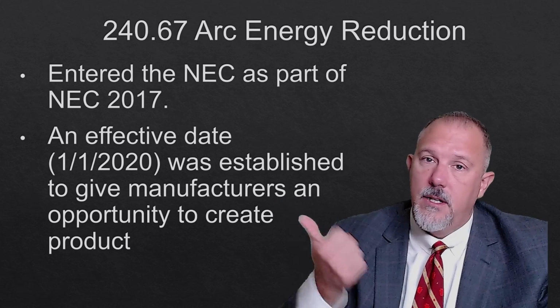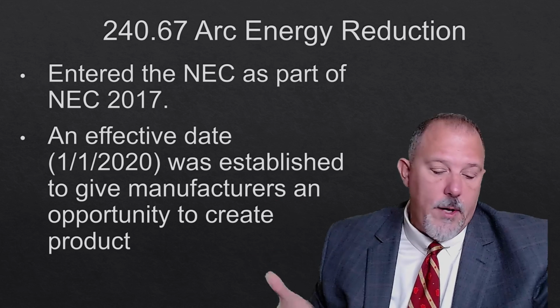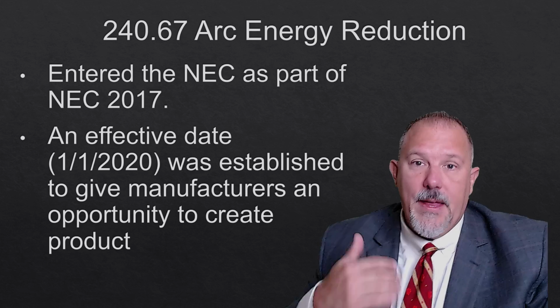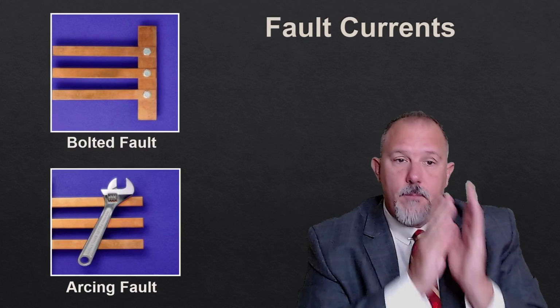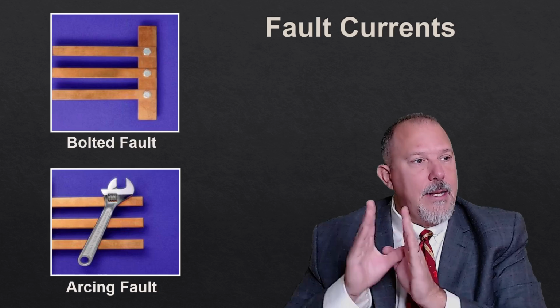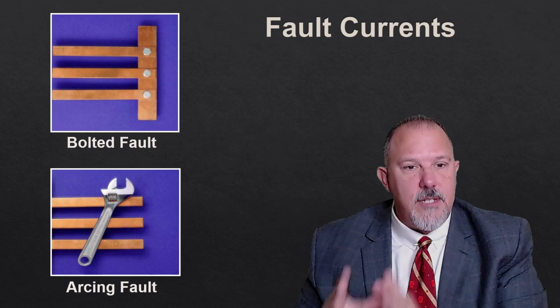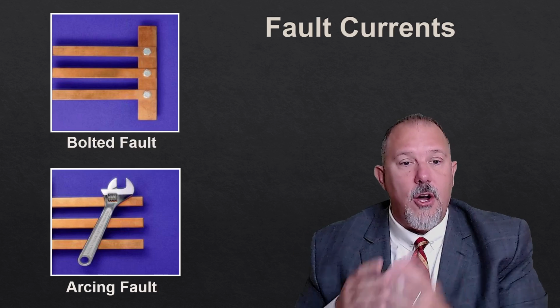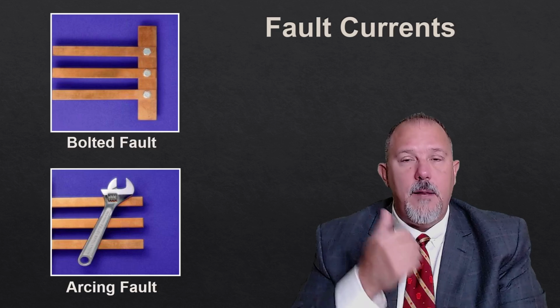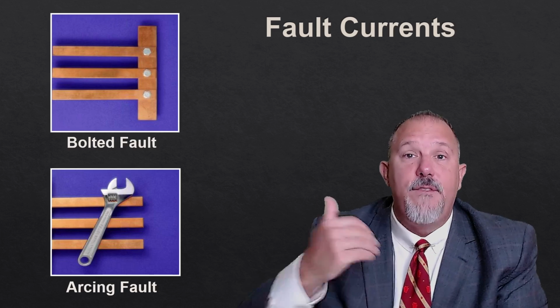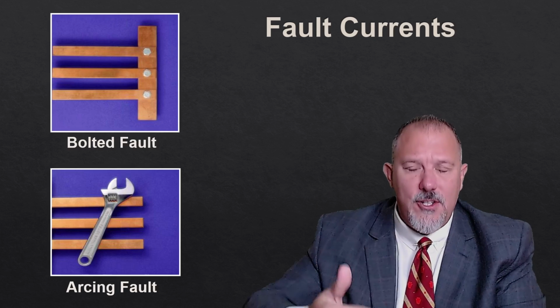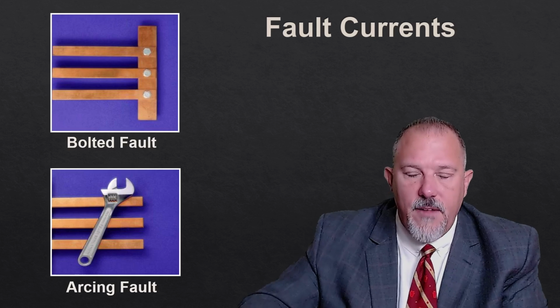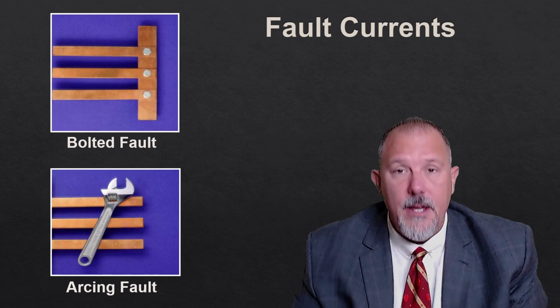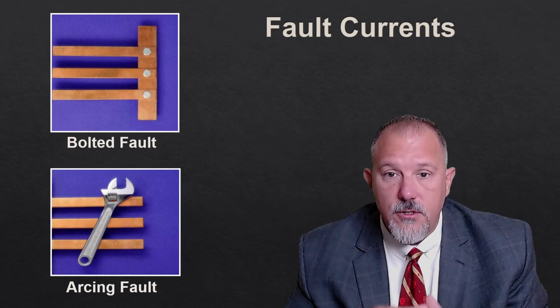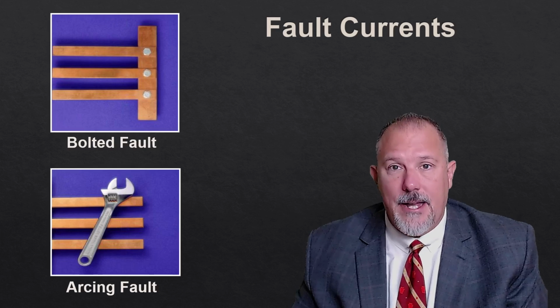They move that time current characteristic curve way over there to the right, and they add delay because you're dealing with two currents. You're dealing with the bolted fault current, but more importantly, in an incident energy application, you're dealing with arcing currents. And arcing currents are calculated based upon IEEE 1584. So if you don't know what IEEE 1584 is, you can look that up. That is the tool engineers use to calculate incident energy.